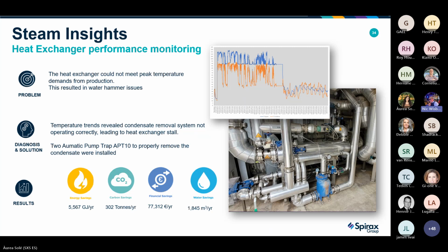And the other challenge with a flooded heat exchanger is that the expansion of steam and water is different. So many of you, if you've got a heat exchanger on site which keeps on popping gaskets, it could be because it's flooded. What that does is warp the plates at different temperatures and different rates, and ends up buckling and eventually breaking the gaskets in between the plates. So we can put a sensor on there, which will then tell you how efficient your heat exchanger is, and when it's entering flood, if at all.